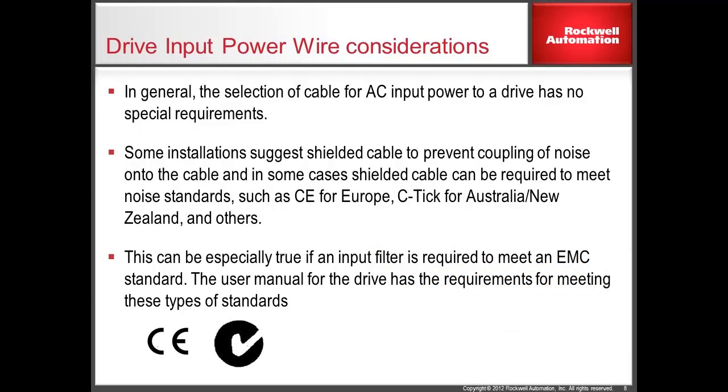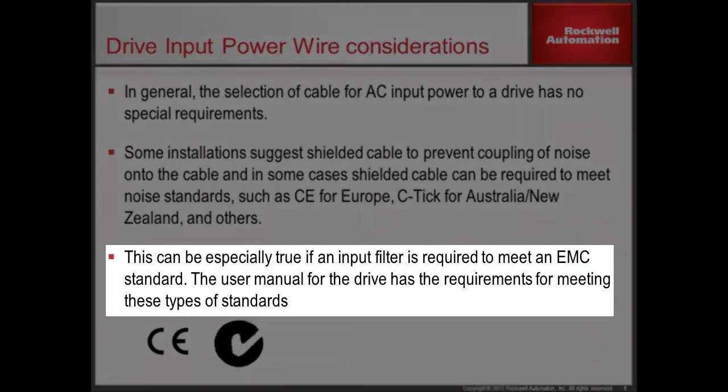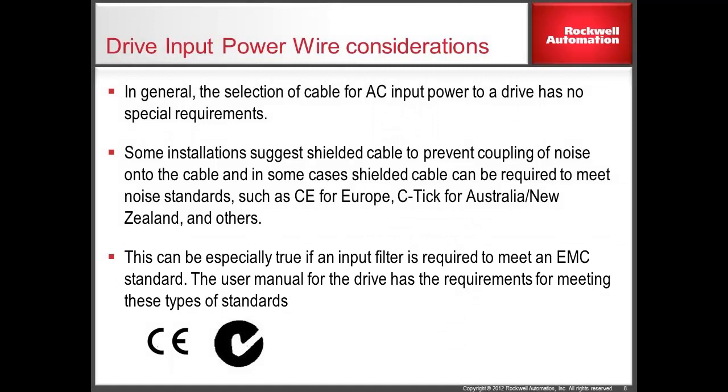When selecting wire to provide power on the input side of the drive, most installations will have no special considerations. Some installations may need to meet electromagnetic emission standards where shielded wire would be required on the input. Examples of this would be CE, C-Tick, or if there is an input filter on the line side of the drive. The installation manual or user manual associated with a specific drive will include additional information to meet EMC standards.